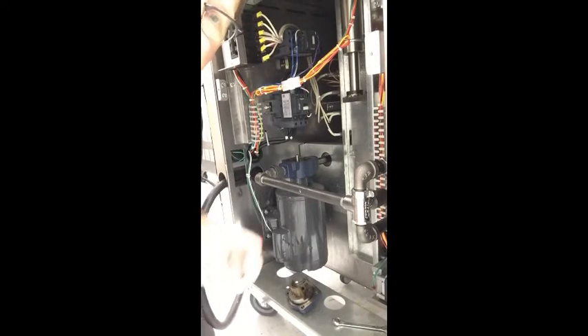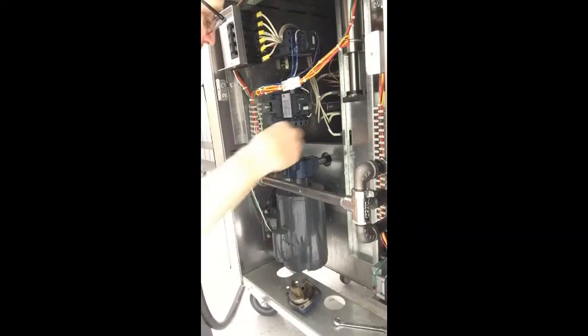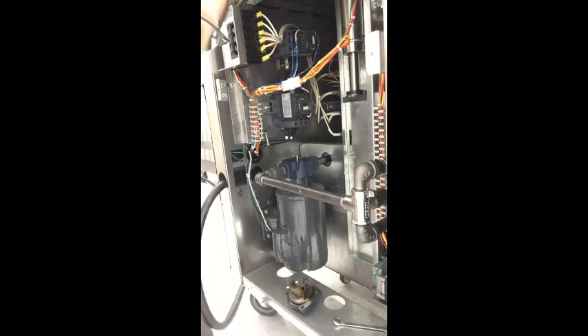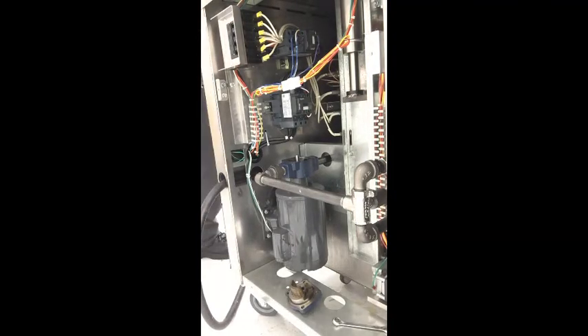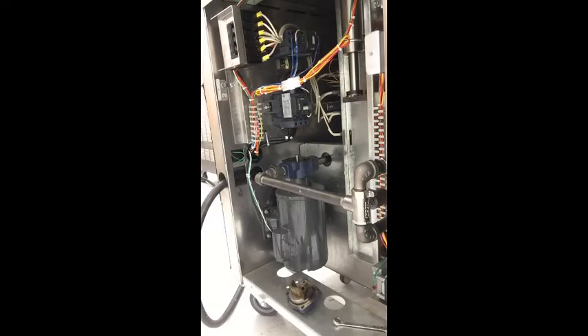But if you'll take a good look right here, you can actually see there is a gear down inside there, right here, and this is a gear pump. So as this pump turns, it churns up all those particles. And for whatever reason, it was not running. Now I'm going to walk around the front real quick and turn the switch on, and we'll allow that to run just a second, to make sure that it's turning. Now that we know that the pump is churning, we know that it should be able to go ahead and pump. So let's go ahead.